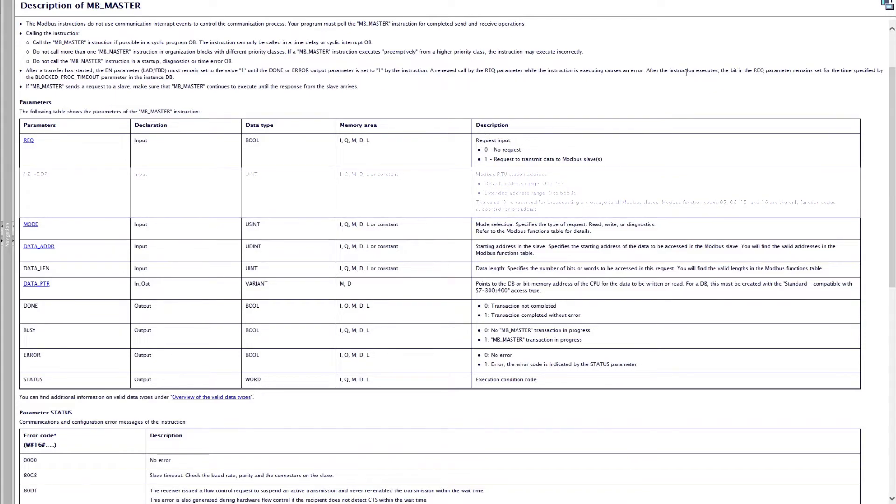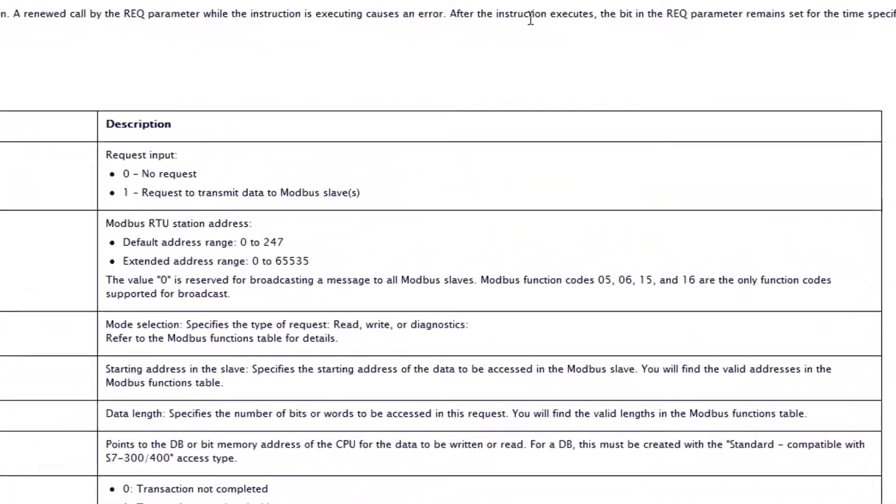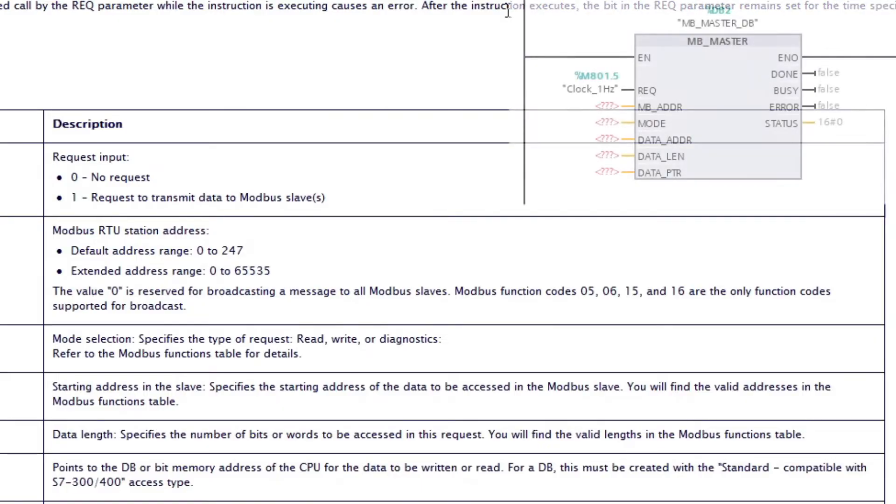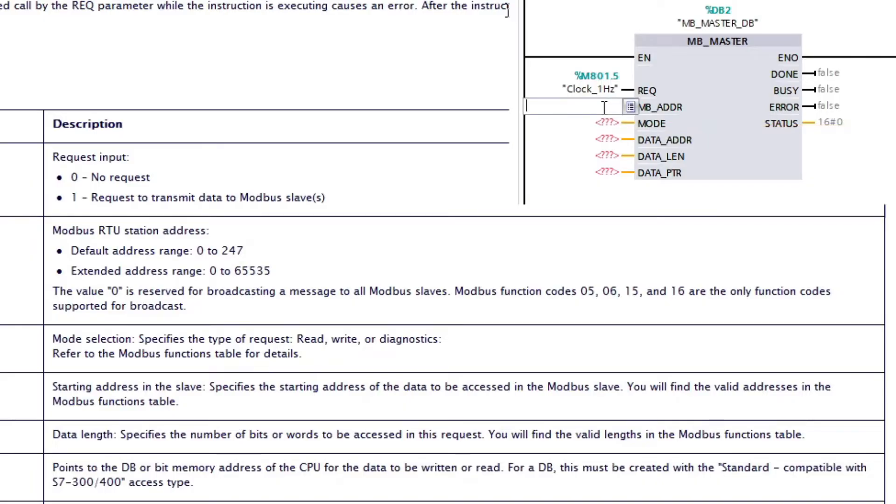Modbus address is basically which slave we want to read from or write to. If we type in value 0 then the block will request to all slaves connected. Else if we want to just request to one specific slave, we choose a specific slave ID. I want to write to Modbus slave ID 5, cause that's what I will set my simulator to.